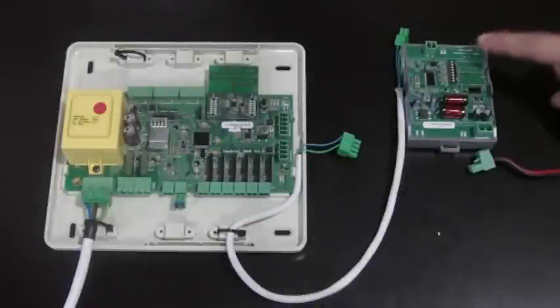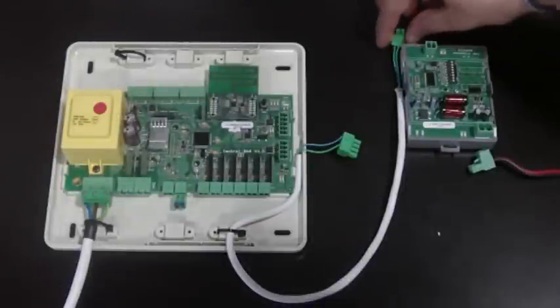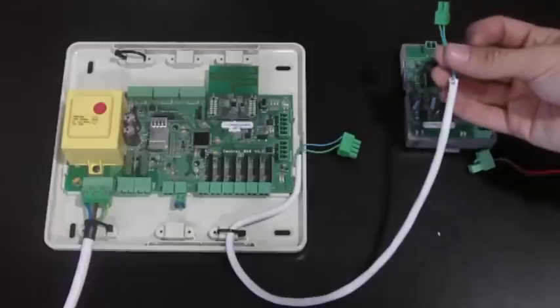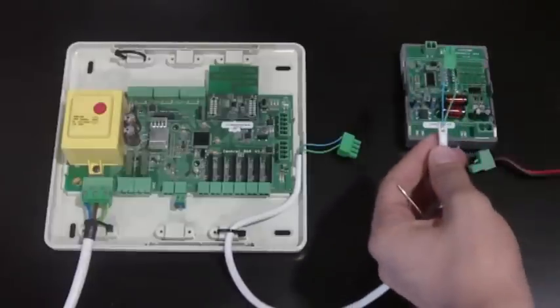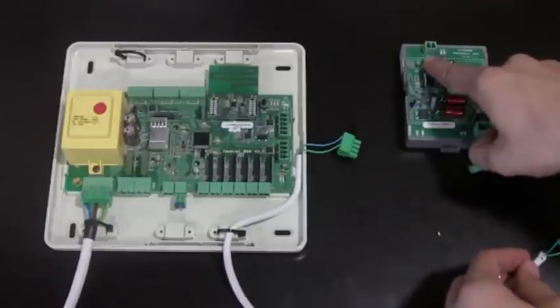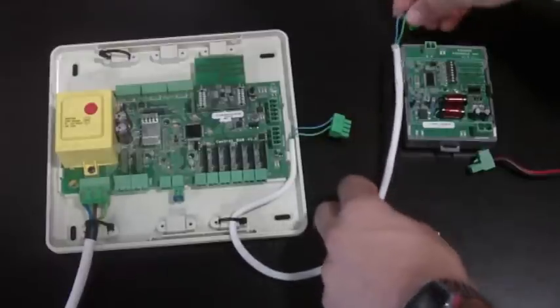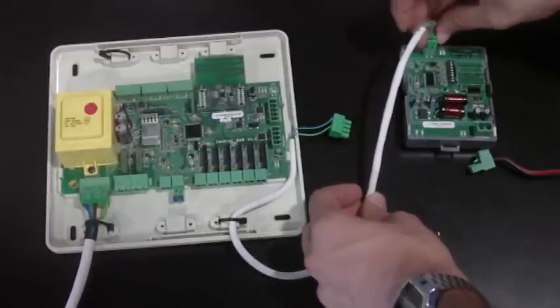The connector on the gateway for connecting the Airzone main controller is a serial two-pin connector. It is very important to respect the polarity of the connections. Bear in mind that this connection on the gateway side is accomplished with a two-pin connector, while on the Airzone main controller side it is accomplished with a four-pin connector.